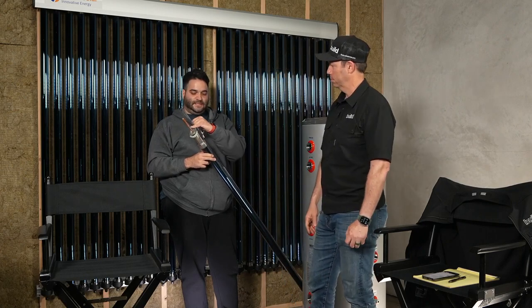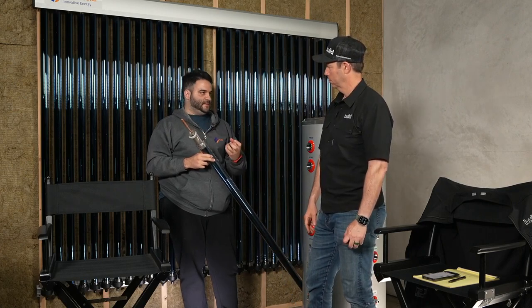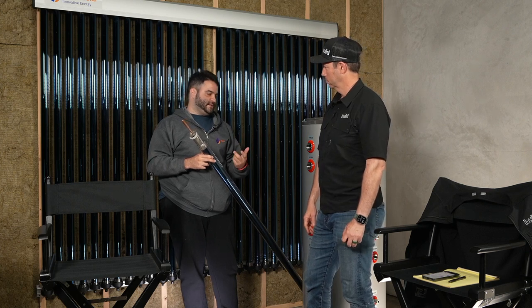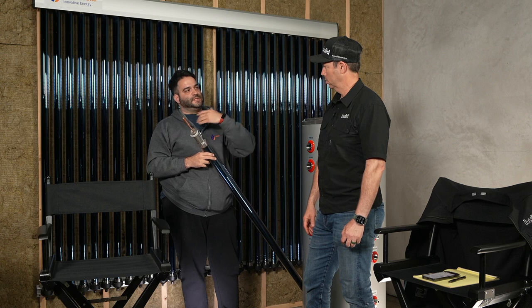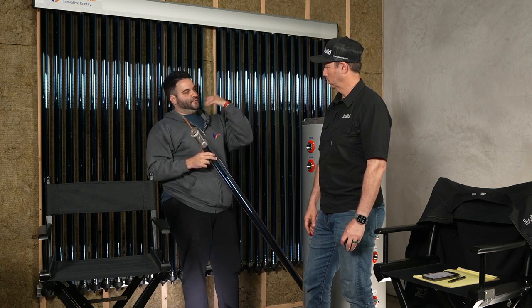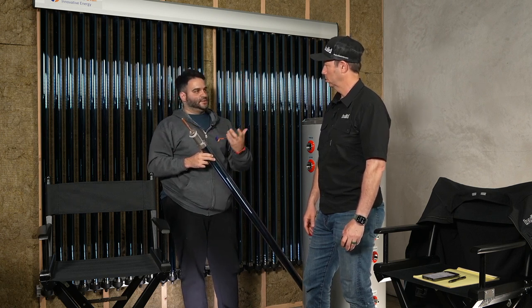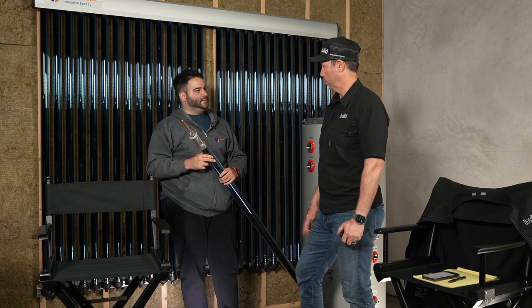Oh, interesting. It heats this copper rod. That glycol, essentially like an ethylene, boils over and becomes a vapor. It goes to the top, so as long as these collectors are manifold upwards, they will start generating energy. They need to be pitched somewhat, basically.